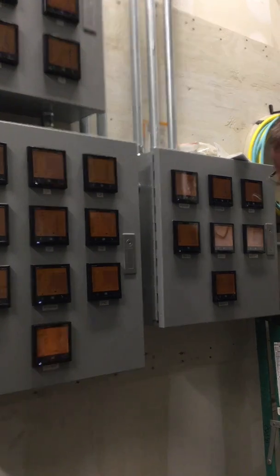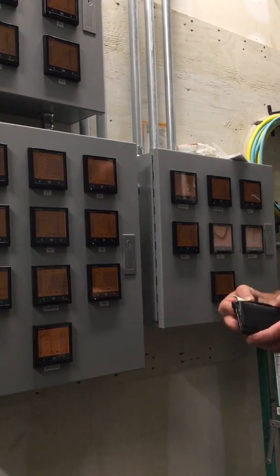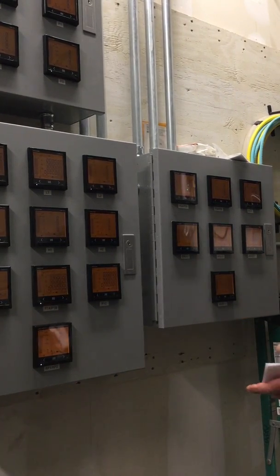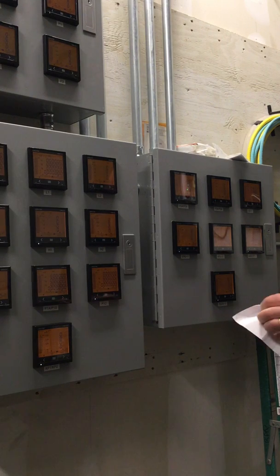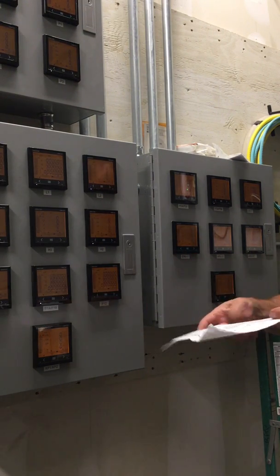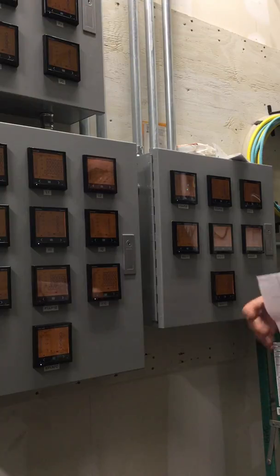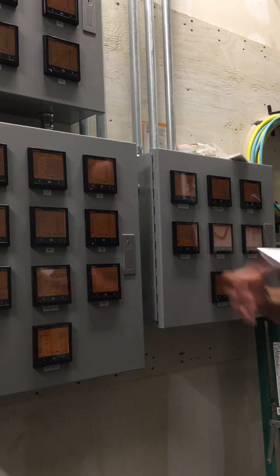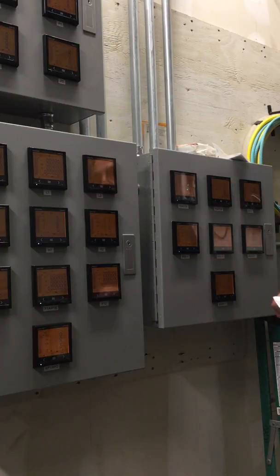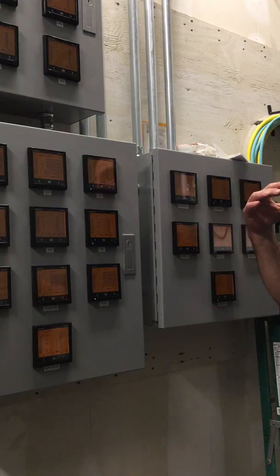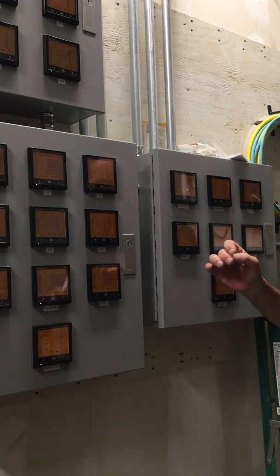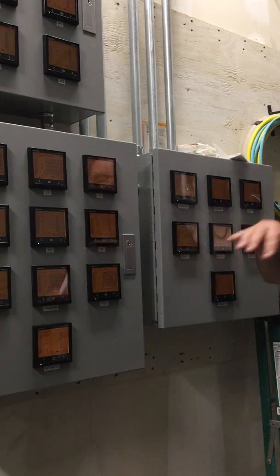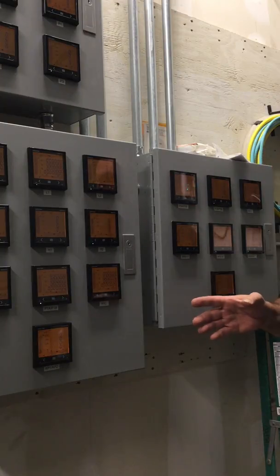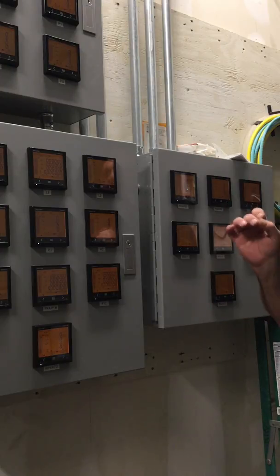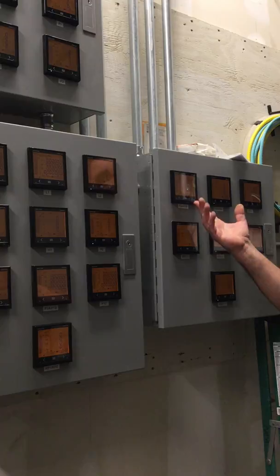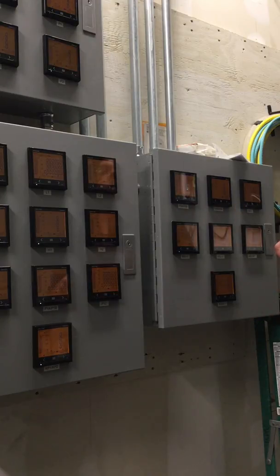CTs were, hold on, because I can't remember everything, so I wrote it down. Oh, here it is. What we got here, meters and enclosures, so most of them are solid core CTs, except for the 2000 amp ones, which are probably in here somewhere, or split cores. So outside of that, programming-wise, don't. In terms of touching them, sure. Okay, you really have to get lucky to get down into the programming level, but it's not impossible. That's the only thing that bothers me. If these things are talking to the BAS, we're going to stop them. We're going to just shut them off from the BAS. Okay? What else?